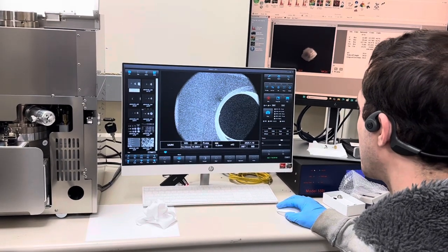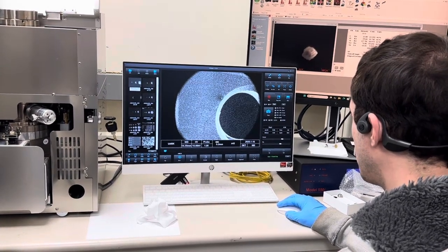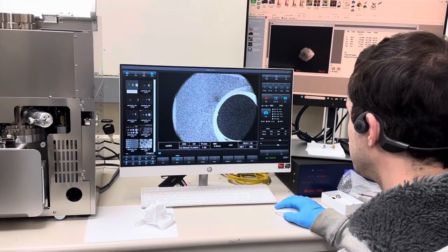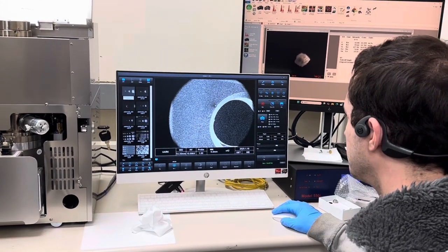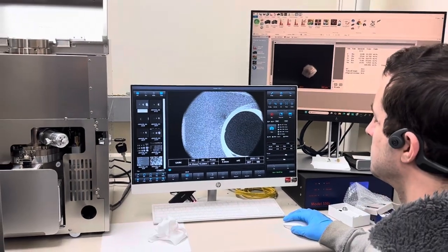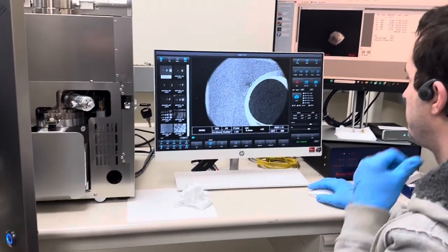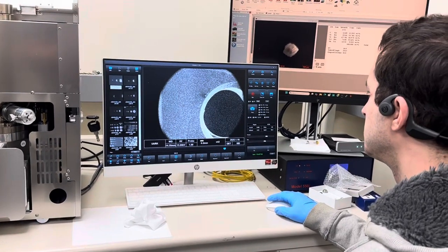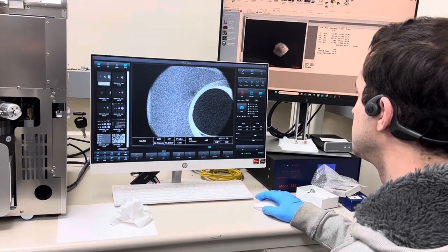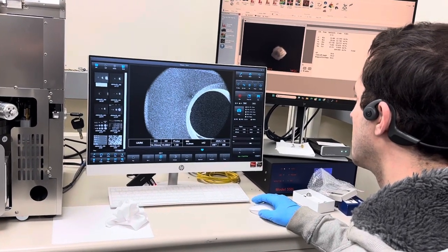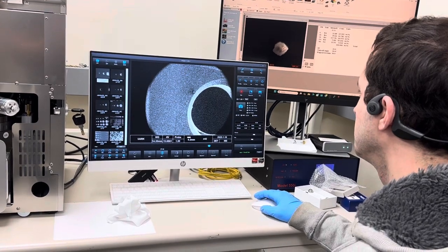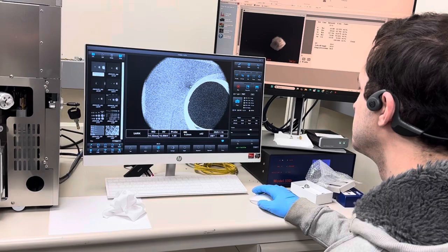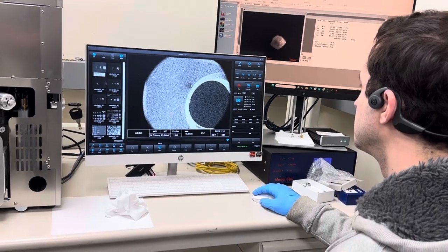It's not really changing that much. Rail it all the way. We picked up more brightness, right? Yeah. So you have to use the whole slider, right? So okay, go to the other gun alignment now. It's getting darker. Yep. So slide it the other way. Keep going. Keep going. Keep going. So we're picking stuff up right there.